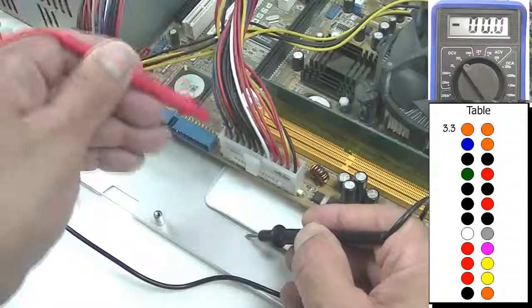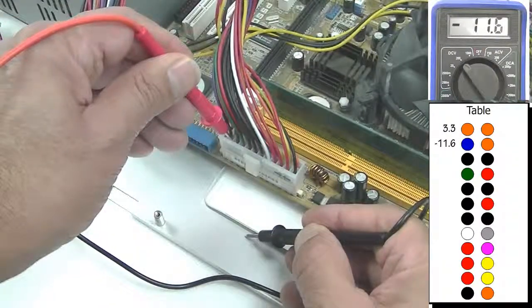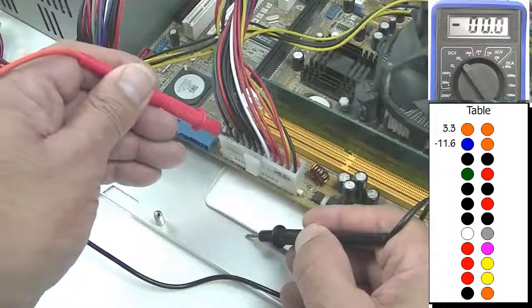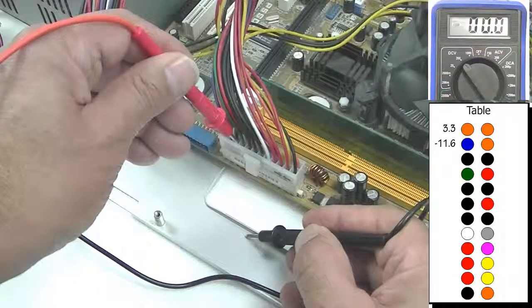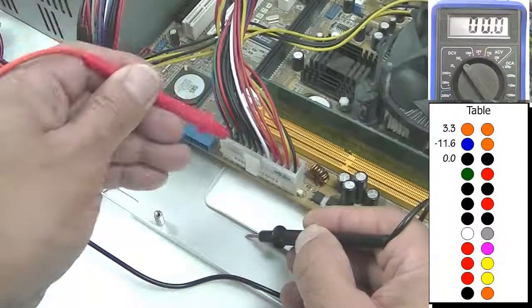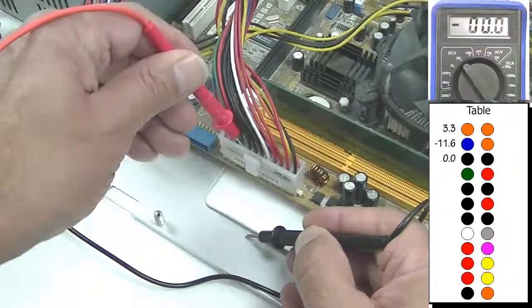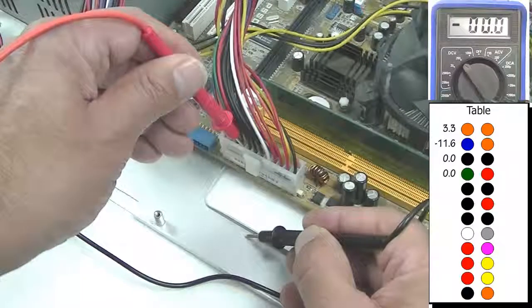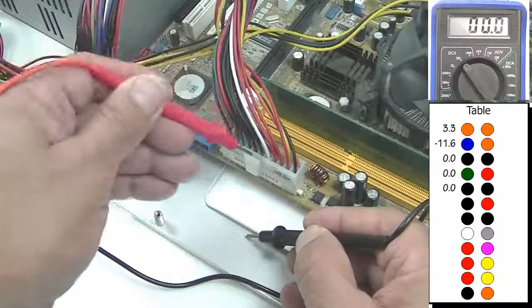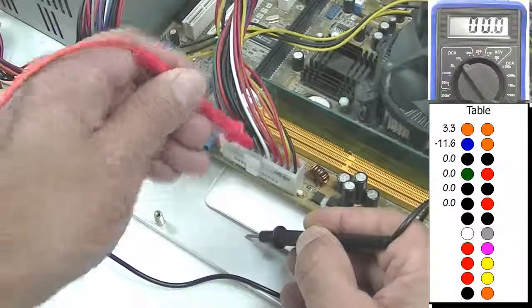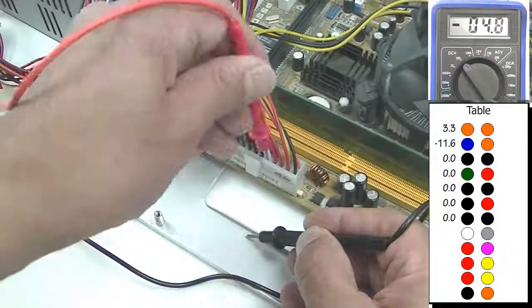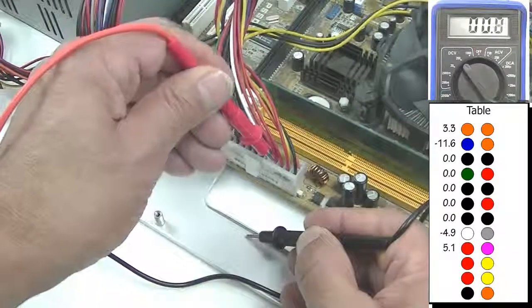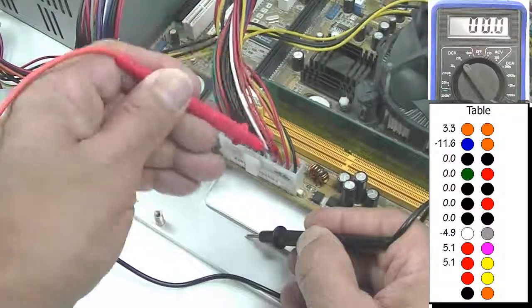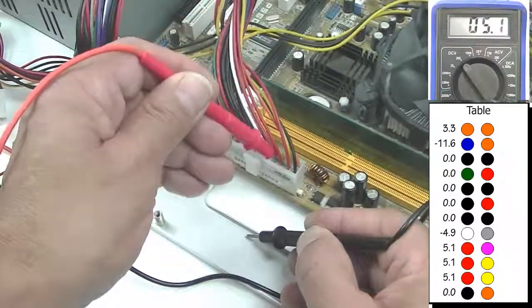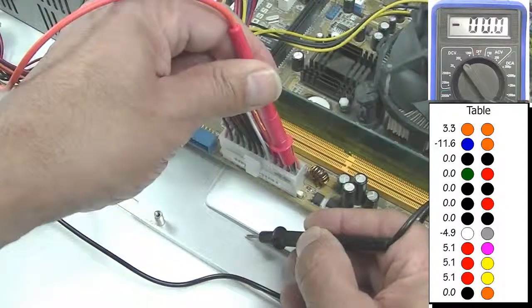Next we check the blue wire, which reads minus 11.6 volts. One of the black wires, connected to the chassis, shows no voltage reading. The green wire, although not connected to the black wire, also reads 0, as do 3 more black wires. The white wire reads minus 4.9 volts, followed by 3 red wires all reading just over 5 volts, and finally another black wire.